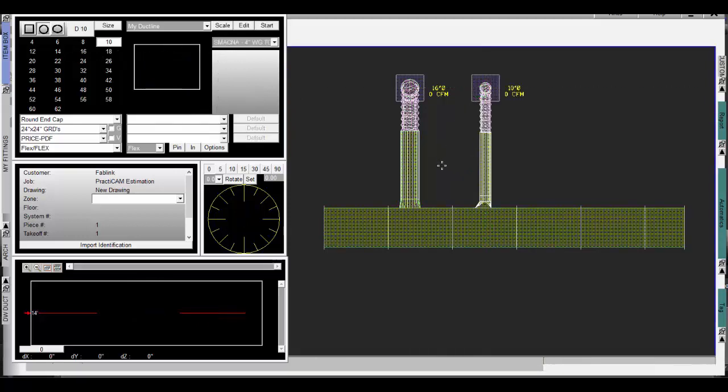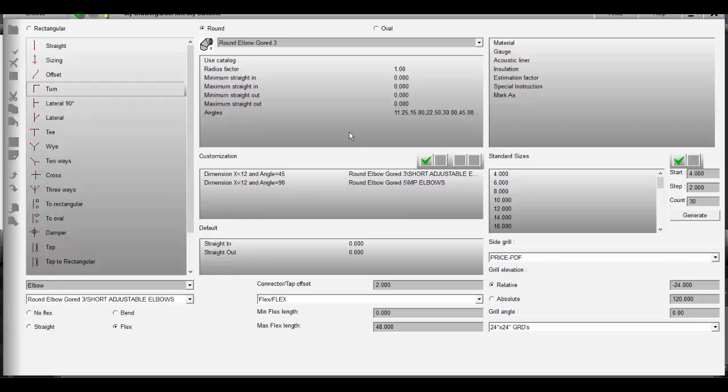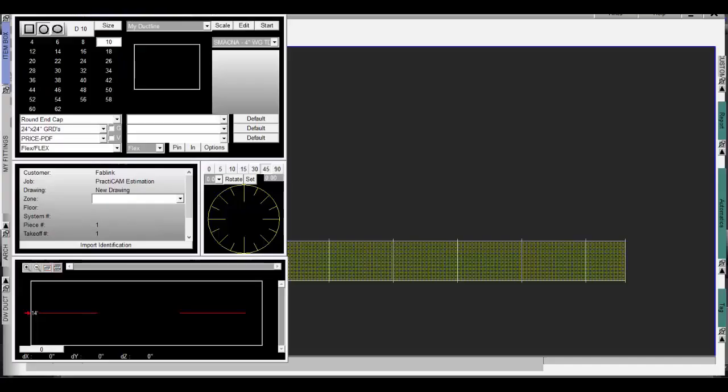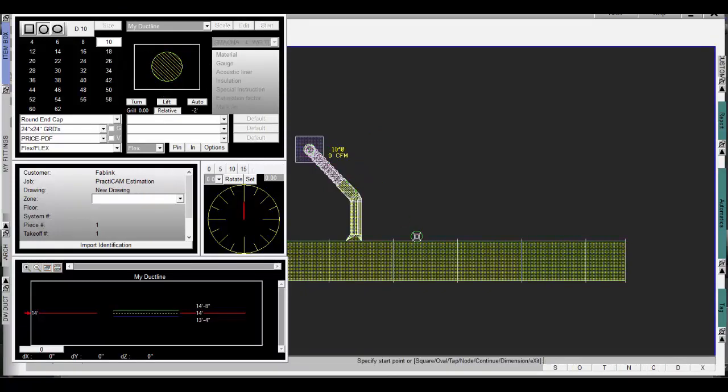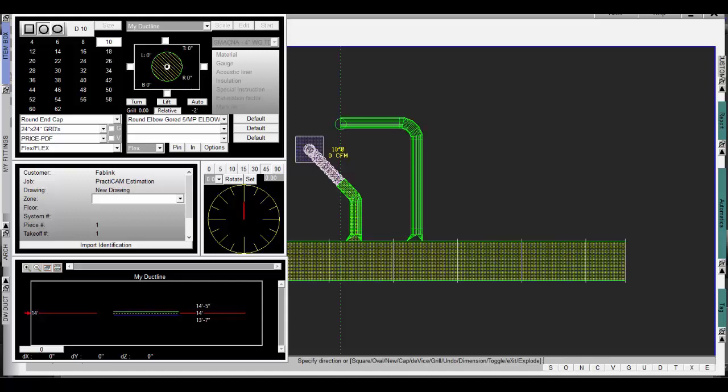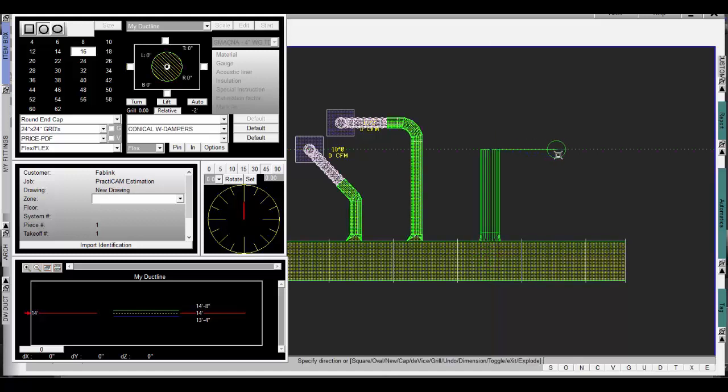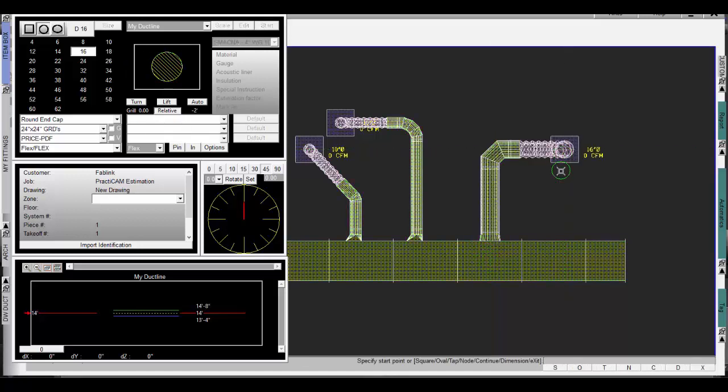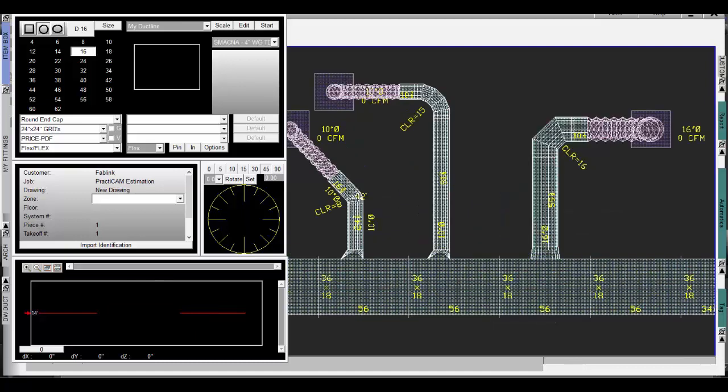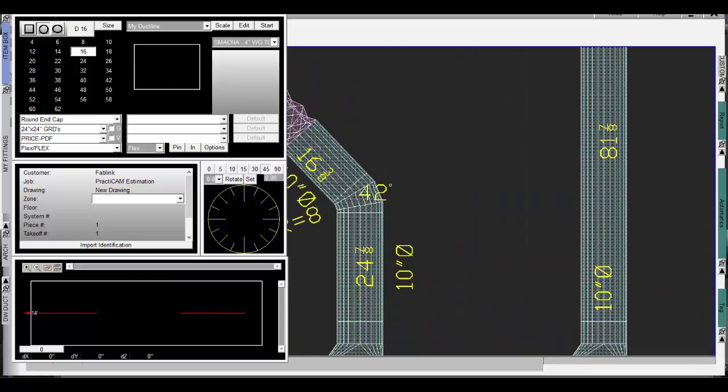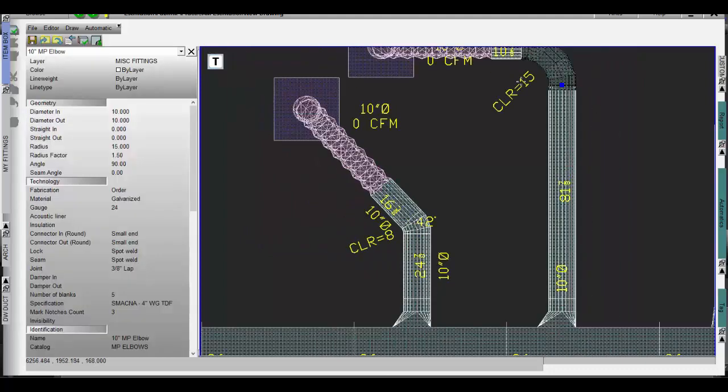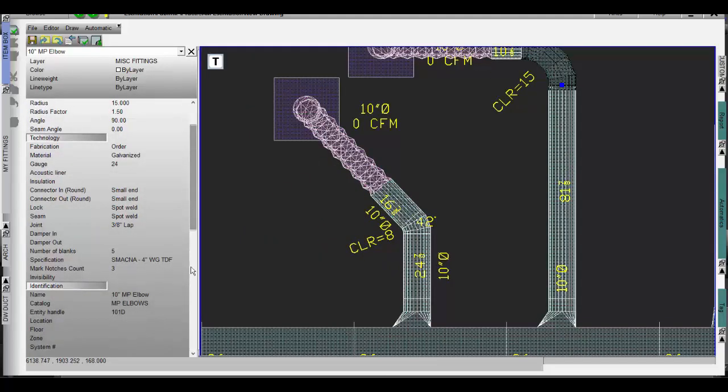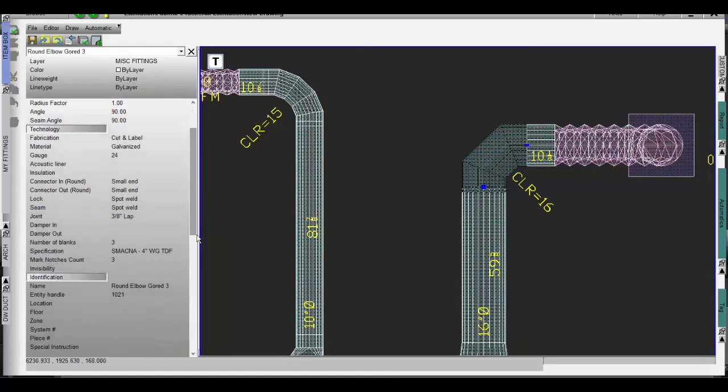In the next example we will choose three different types of elbows. First if diameter is less than 12 and angle is 45 degrees we use a short adjustable L that will be ordered only. If diameter is less than 12 and angle is 90 degrees we'll use a medium pressure elbow also ordered and the round elbow gored 3 at the top. This is our default in case our conditions aren't met. Coming out to the drawing window we will use the Ductline to auto route a 10 inch 45 degree elbow. Then we will auto route a 10 inch 90 degree elbow and lastly a 16 inch elbow running out to a GRD. Then we will explode the Ductline and apply auto tagging to the run so we can see our sizes. Notice as we click the first elbow it is the correct short adjustable L that is ordered. The second one is the proper medium pressure elbow which is also ordered and finally the round elbow gored 3 will be cut and labeled meaning fabricated. The Ductline fitting selection is completely automatic.